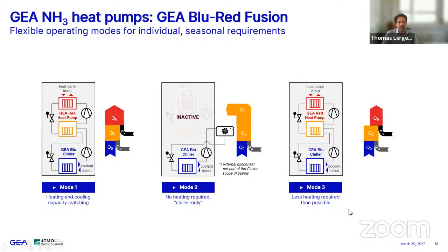If you need less heating capacity, then based on your temperatures and on your cooling capacity, you can regulate your heat pump stage. It looks like this: the heating capacity is less than it would be if you look at the first mode. And there's a surplus of intermediate capacity from the chiller stage which is not necessary for the heat pump stage, and you can reject this through the secondary condensing system. So basically you have a parallel use for this intermediate capacity. The part that is needed goes into the heat pump, and the part that is not needed goes through this secondary external condensation system.